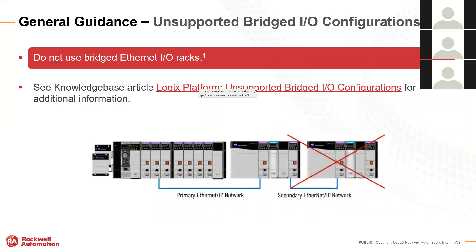Bridging networks is not supported in redundancy. The example shown — going from an EN2TR in slot zero to one in slot four of a remote IO chassis to then go to another chassis — might technically function, but it is not supported in a redundancy configuration. Don't attempt it. In practice, this situation is rarely seen in the field.